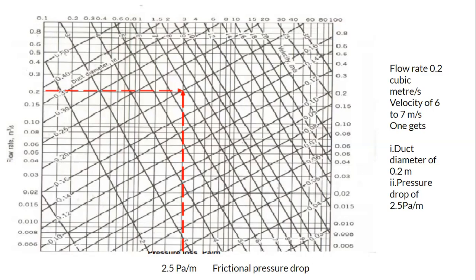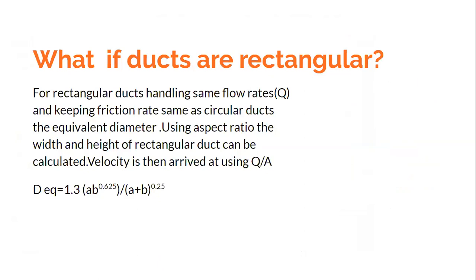Now, what if the duct is not circular? This friction chart is valid only for circular ducts. If it is a rectangular duct, we need to use the concept of equivalent diameter. Equivalent diameter means the diameter that would give you the same flow rate and same friction rate as the circular duct.